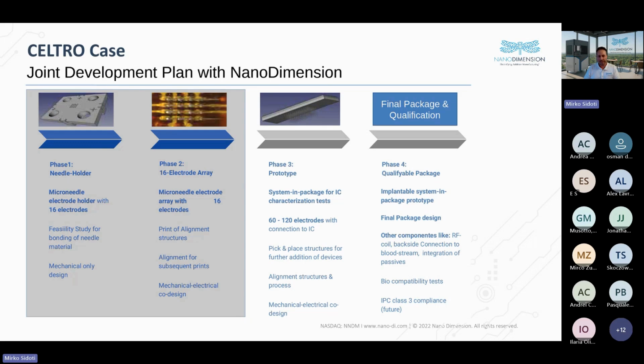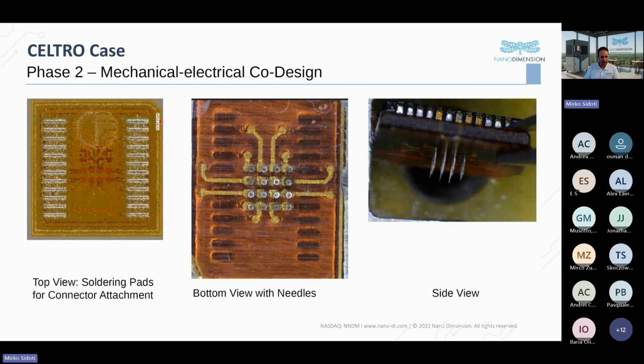We completed phase two. Phase three is ongoing, and phase four will require, of course, the full qualification of the process. So between phase two, which is the proof of concept, and phase three, the main difference is to go from proof of concept with only 16 needles to a higher number of needles to harvest the energy that is really the energy they need for pacemaking application. This is the structure that we built, and especially on the right picture, you can see the needles sticking out of the dielectric structures. And from the image in the center, you see the connection between each and every needle, each and every element of the array of electrodes, which is made using the conductive ink.